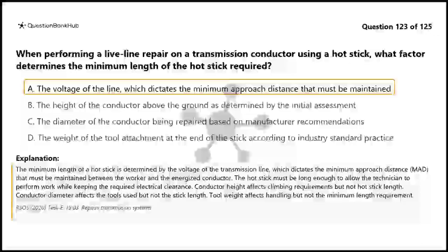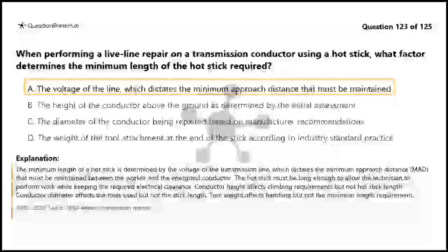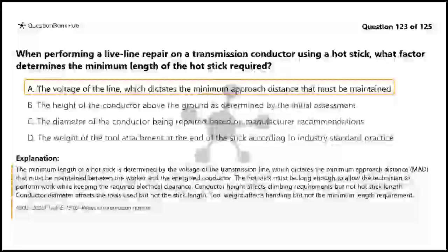The minimum length of a hot stick is determined by the voltage of the transmission line, which dictates the minimum approach distance, MAD, that must be maintained between the worker and the energized conductor. The hot stick must be long enough to allow the technician to perform work while keeping the required electrical clearance. Conductor height affects climbing requirements but not hot stick length. Conductor diameter affects the tools used but not the stick length. Tool weight affects handling but not the minimum length requirement.